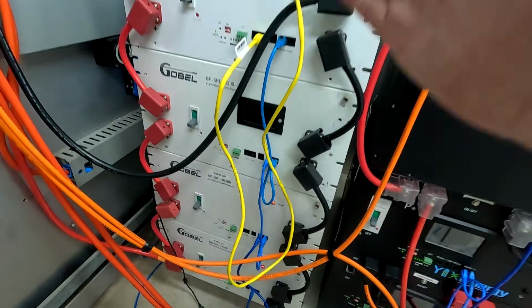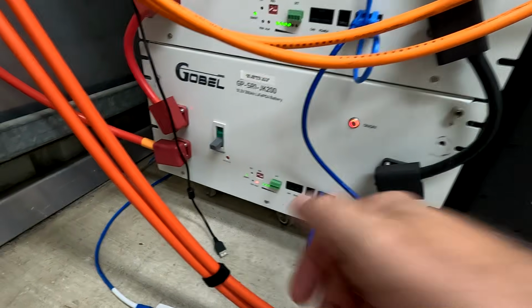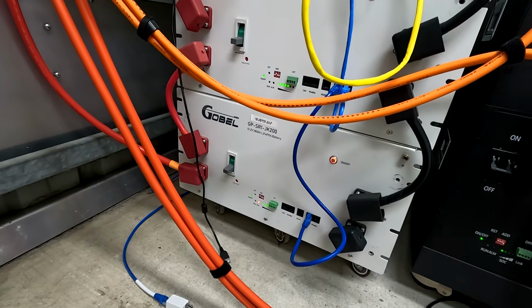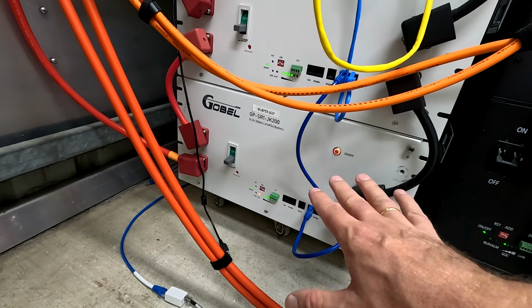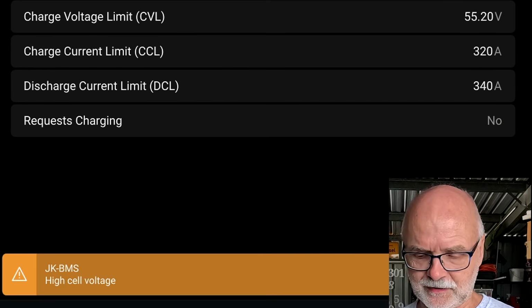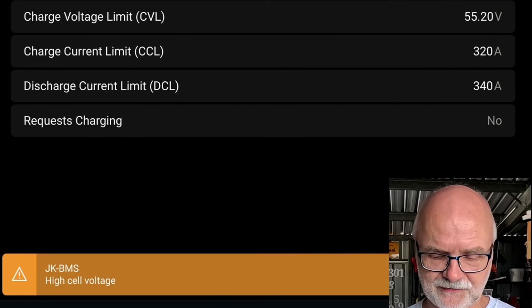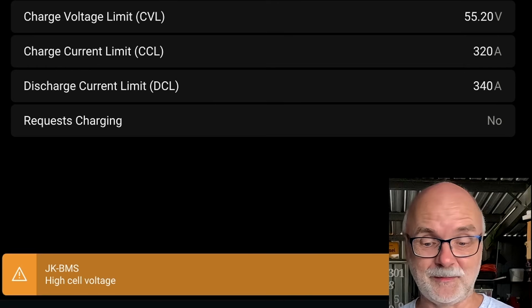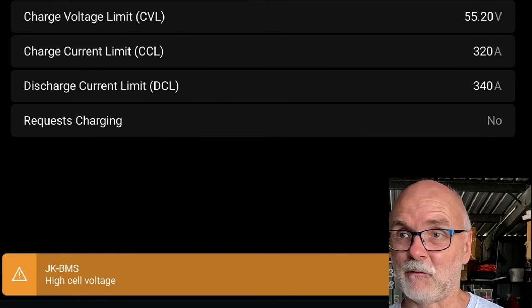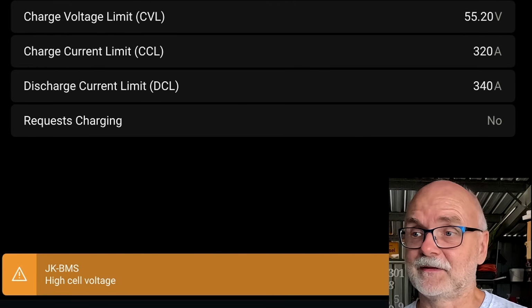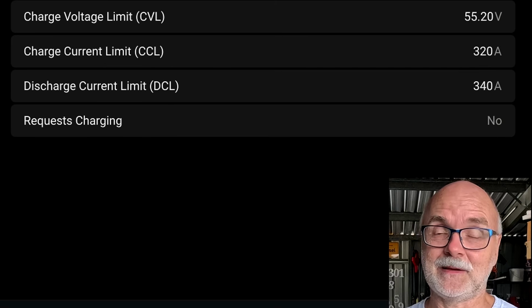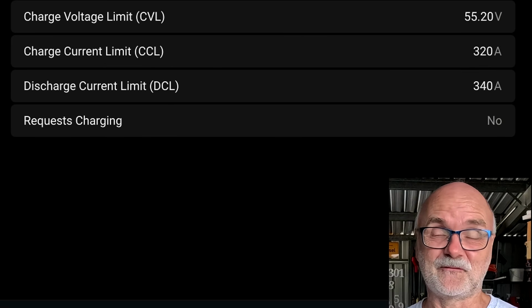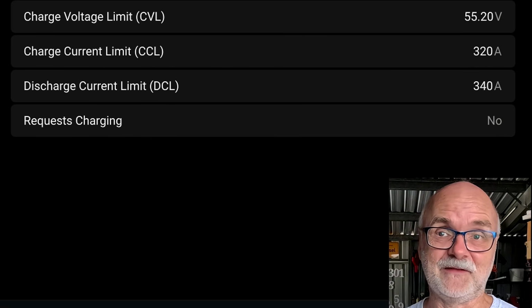So this works all very well, and we can also see our GoBel tower stack here, and the bottom battery has an alarm there. So you also have a visual indication that something is wrong with this battery. Okay, I've now changed the settings again in the BMS, and we can see we have now the correct charge current again, the CCL. The charge MOSFETs have turned on in the BMS again, and we can charge with full power of 320 amps. So as soon as the fault clears in the BMS, the master BMS requests the full CCL and DCL again from the inverter.